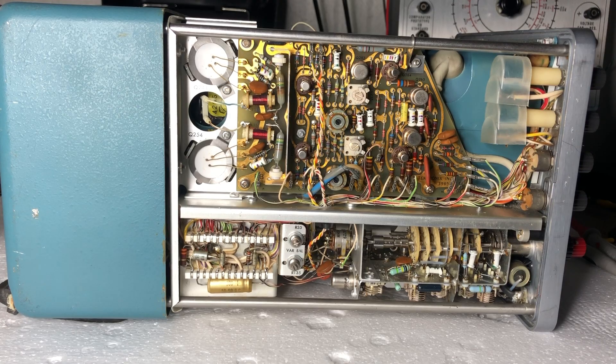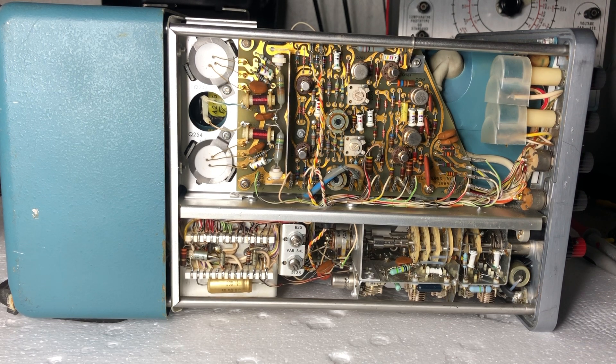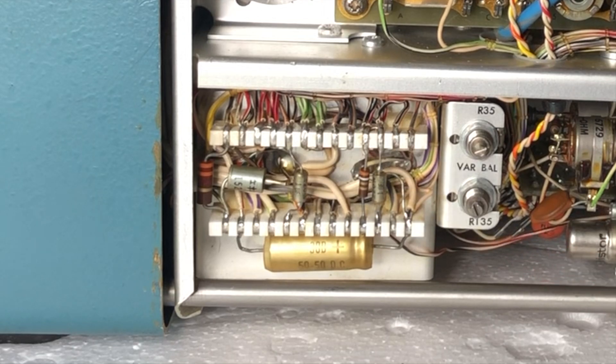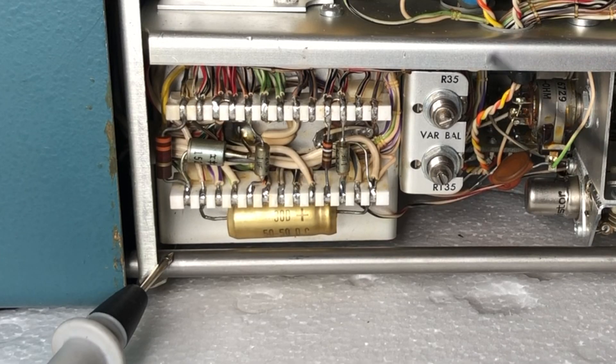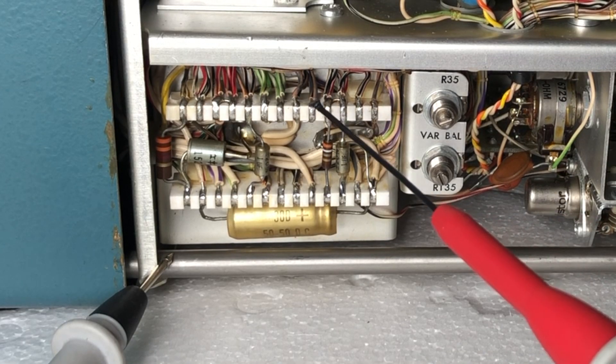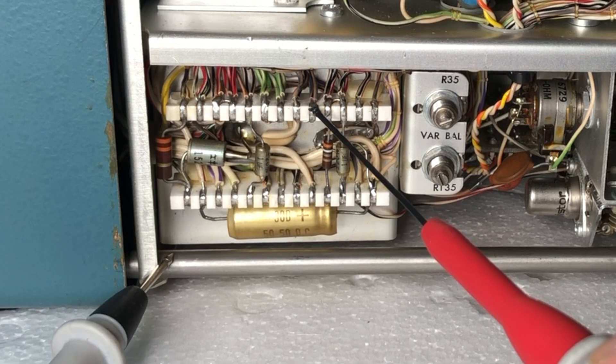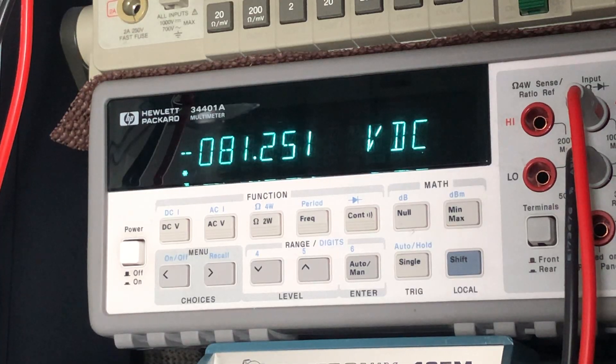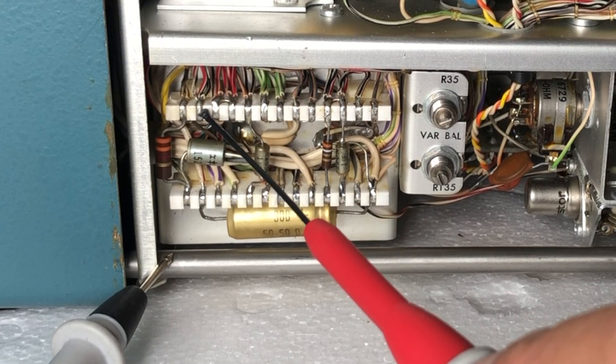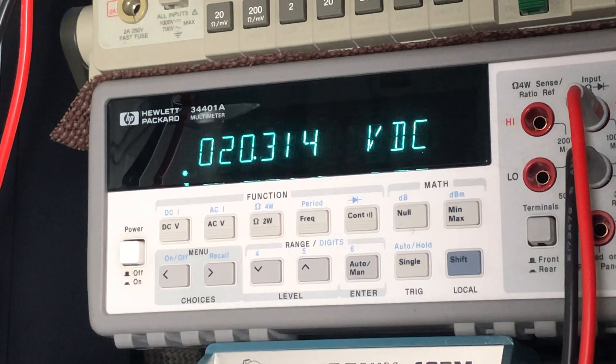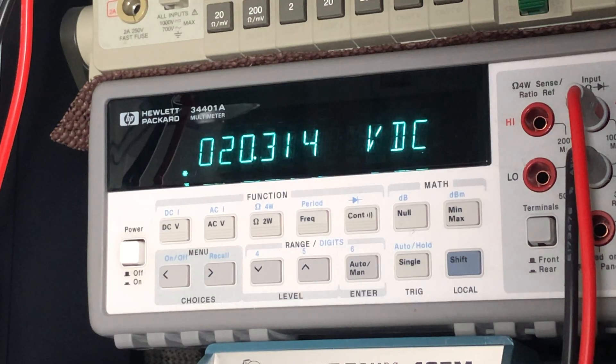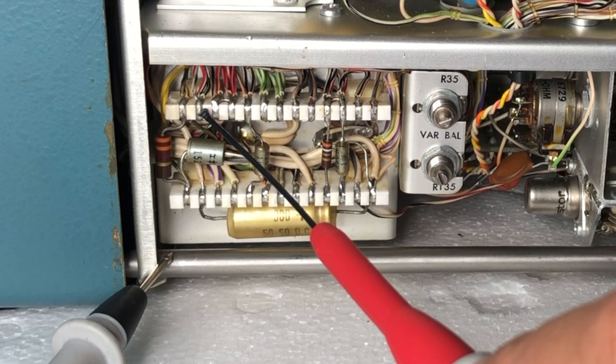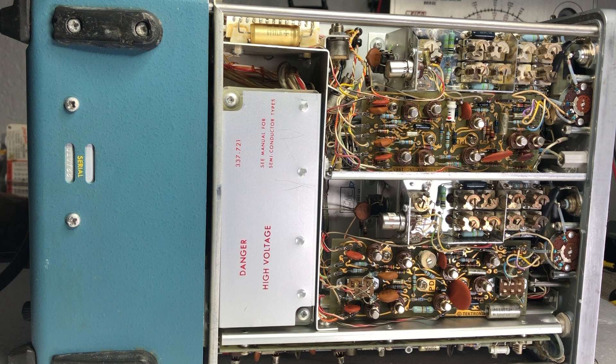That's the reason we need to test it at the indicator unit as well for the right power supply voltages. These are the test points which we're going to test now. There are two voltages which we need to test here: 81 volts right here and 20 volts right here. And I have both of them right up to the spec.